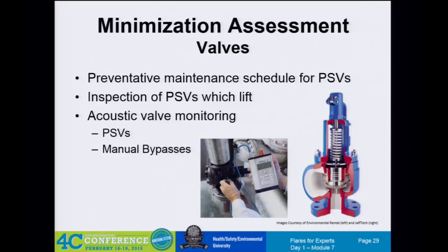You definitely want to document how you are minimizing leakage from PSVs. Most of you have OSHA requirements for inspection of PSVs. Document that. Or if, say, a PSV opens and closes, do you have a procedure to go back and check to make sure that valve reseated properly? Many times people say, yeah, we'll go by and maybe shoot it with a temperature gun. We ask, is there a procedure for that? No. It's just something, do you do that all the time? Well, probably most of the time. But it's more about formalizing that procedure.